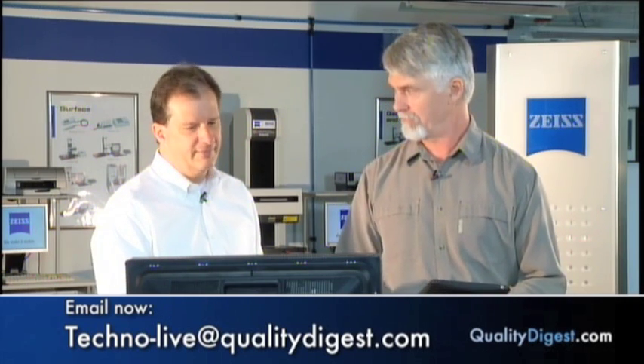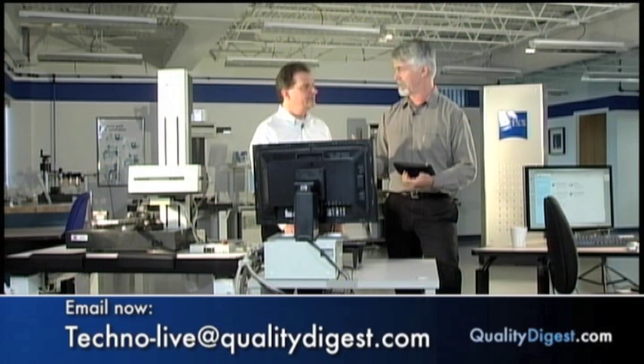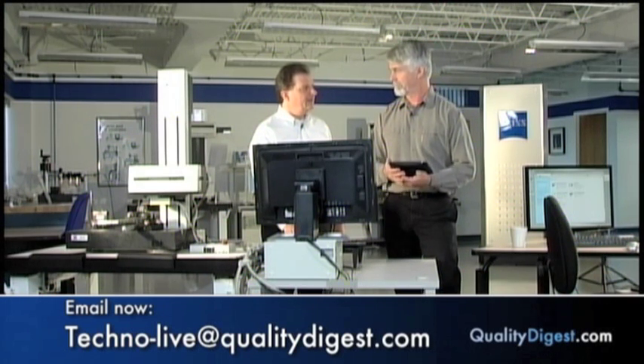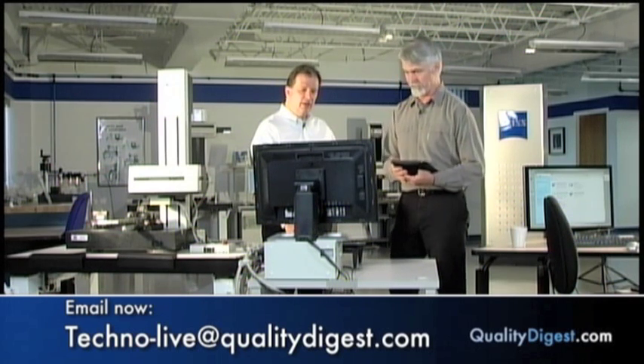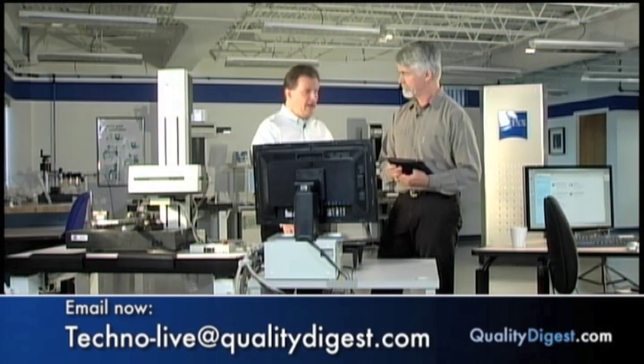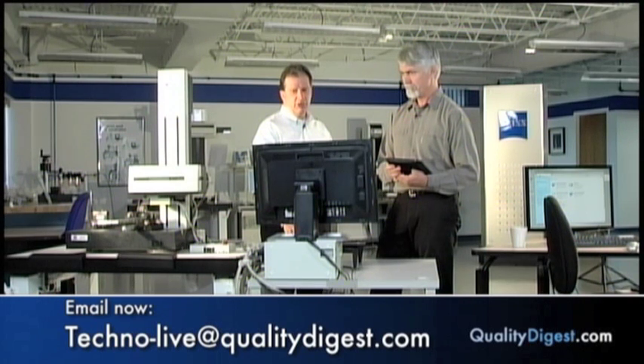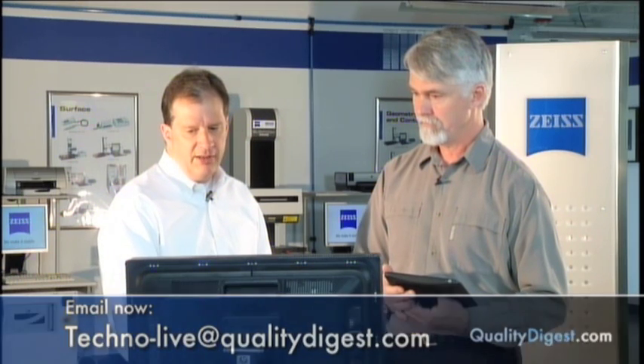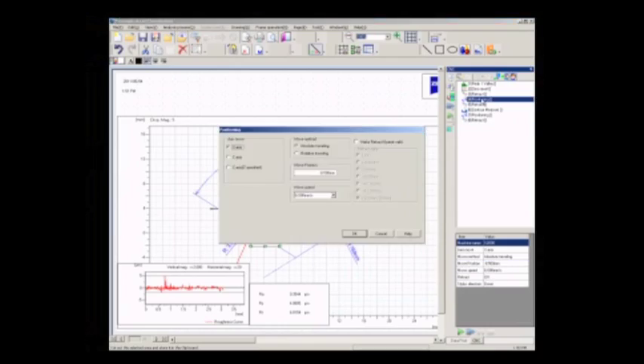And that, and the calibration stuff you mentioned, makes the ACCTee a brand new beast. Another nice advantage with the ACCTee software with the part programs is the ability to easily edit the part program. For example, if I needed to edit this position, all I have to do is double click on it, and it brings up the very dialog I used to create that feature. And so all I would have to do is change the position, for example, or change the speed here, click OK, and I've edited my program.